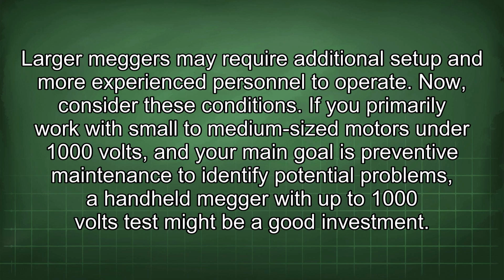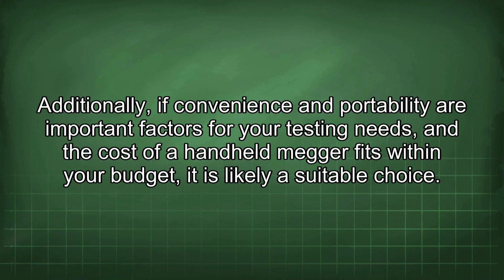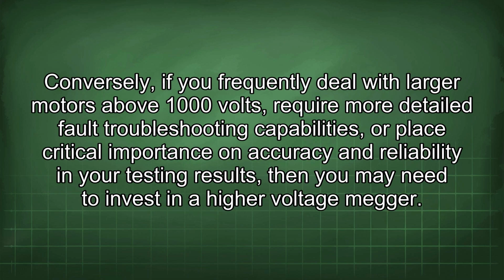Now, consider these conditions. If you primarily work with small to medium-sized motors under 1000 volts, and your main goal is preventive maintenance to identify potential problems, a handheld Megger with up to 1000 volts test might be a good investment. Additionally, if convenience and portability are important factors for your testing needs, and the cost of a handheld Megger fits within your budget, it is likely a suitable choice. Conversely, if you frequently deal with larger motors above 1000 volts, require more detailed fault troubleshooting capabilities, or place critical importance on accuracy and reliability in your testing results, then you may need to invest in a higher voltage Megger.